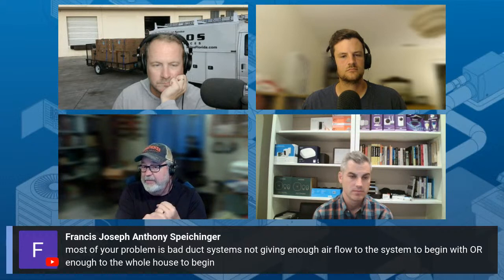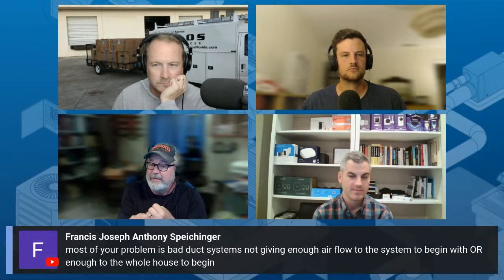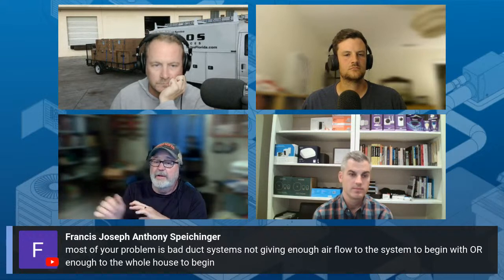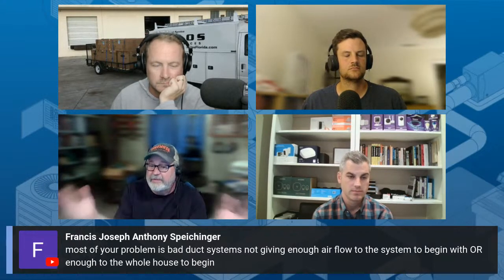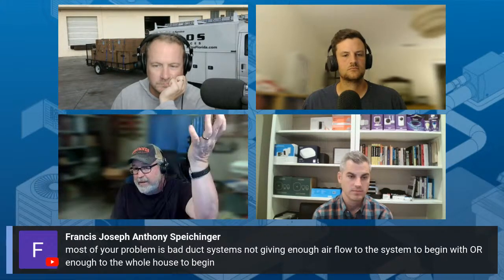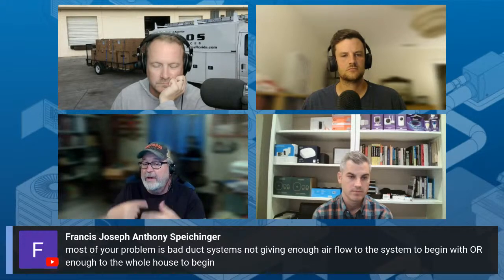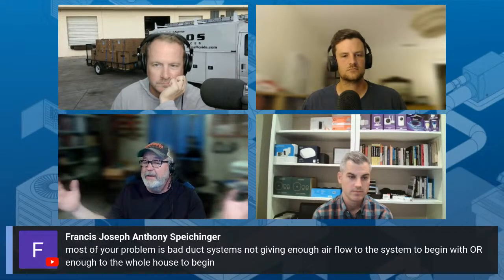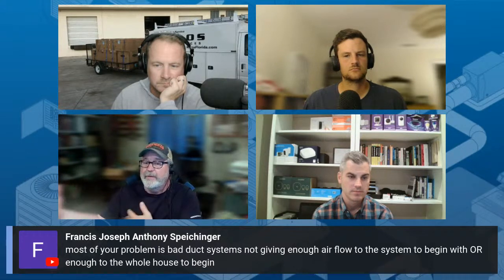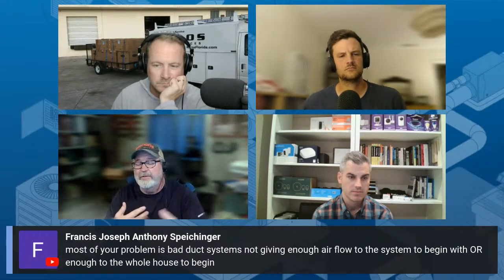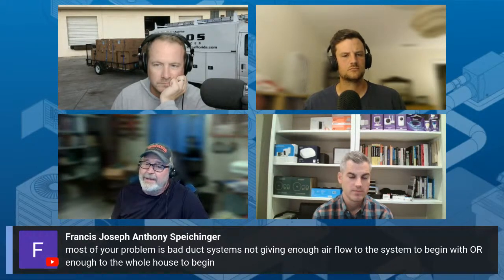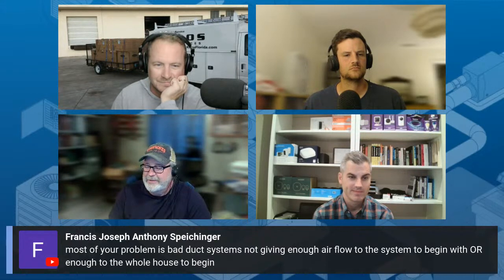And then, of course, that's all dependent upon equipment sizing. If you oversize the equipment, you're going to have short cycling, and it's going to run for a short period of time, and then it's going to stop, and then the air is going to separate. It's going to stratify. But the longer those cycles run, the better mixing you have. It gives more time for the air to circulate through the entire system several times. So I can't emphasize enough the whole airflow issue. I go into a lot of detail in the classes that we teach.